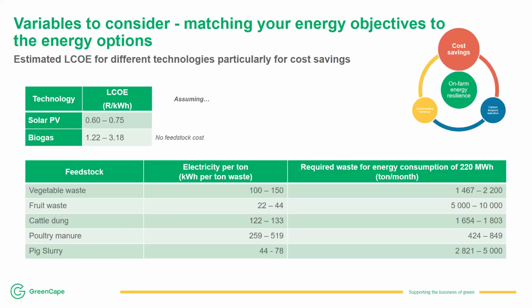Again, if we're just going to look at the LCOEs, it's important to acknowledge and compare what sort of price you're looking at for your different technologies for different energy objectives. So for instance, if we are looking at solar PV and biogas, which are the only technologies that would be applicable for your cost savings, we see that the LCOE for solar PV is between 0.60 to 0.75 rands per kilowatt hour, versus biogas, which is 1 rand 22 to 3 rand 18 per kilowatt hour.